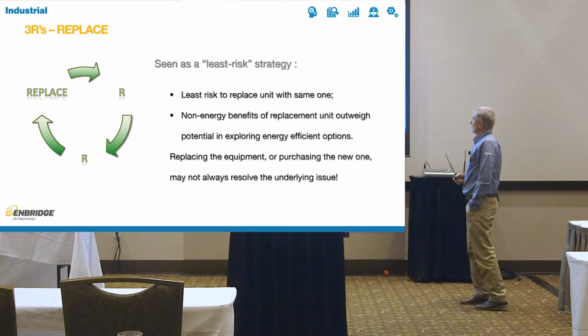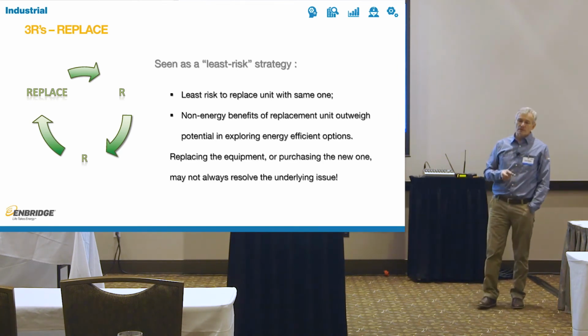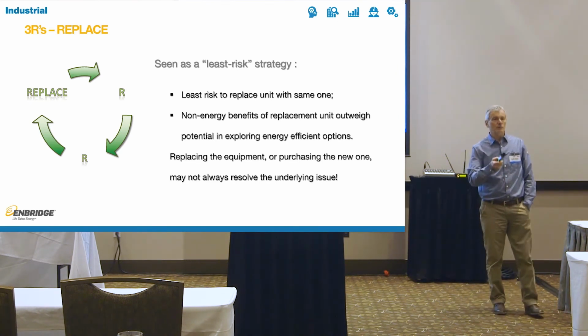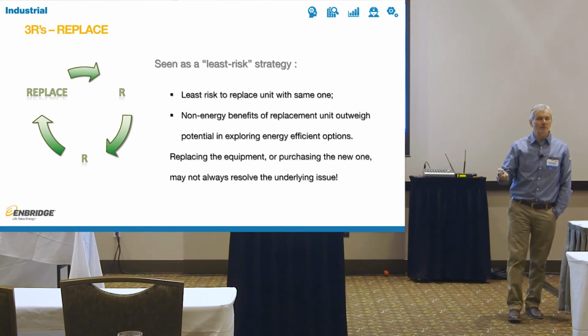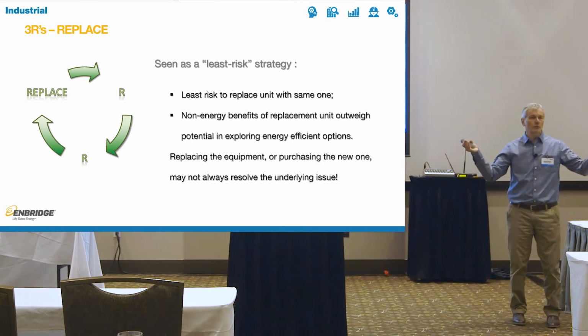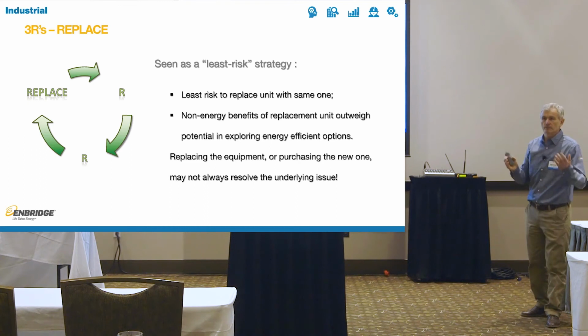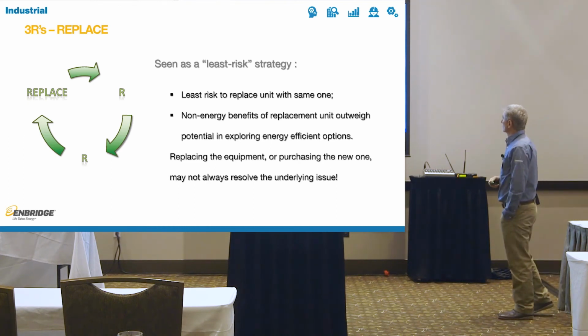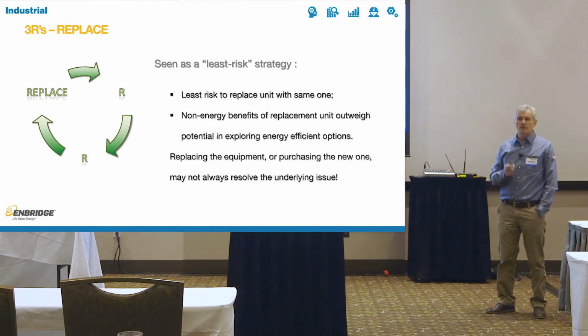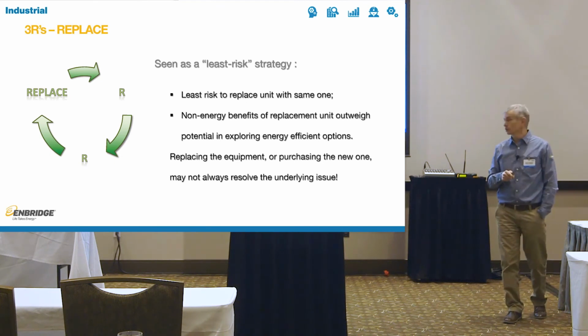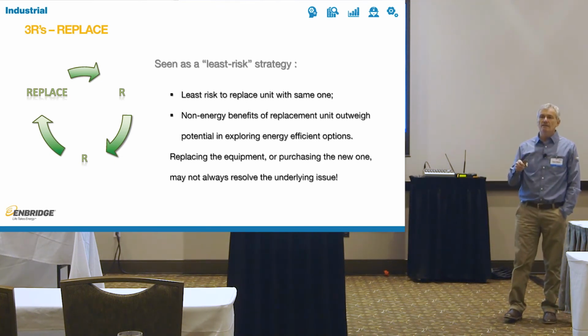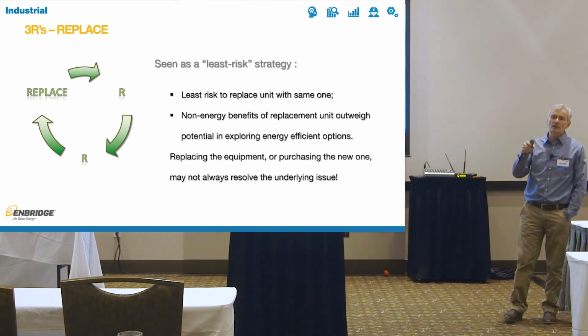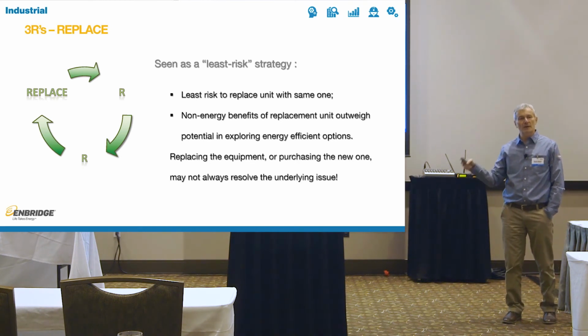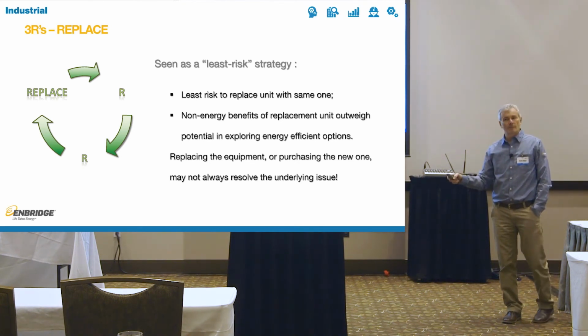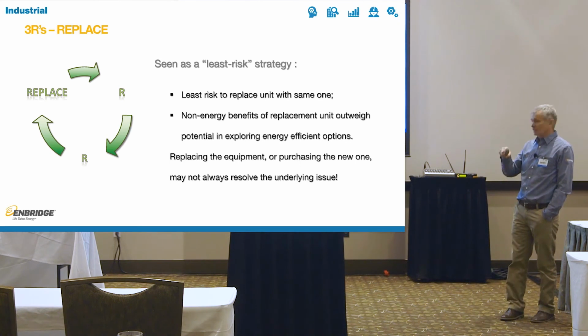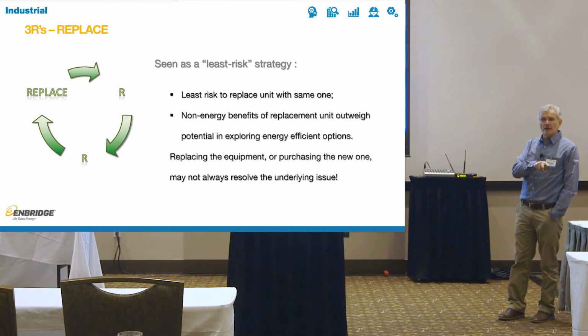It's a least risk strategy because, as everybody here knows, if you replace the unit with an identical one, nobody will ever blame you for anything. That's the way it was, that's the way it is now, I didn't do anything, period. But the problem is that you don't realize all the potential savings. And the rub is that you may not actually solve the problem that the old piece of equipment had. And then that doesn't resolve underlying issues.